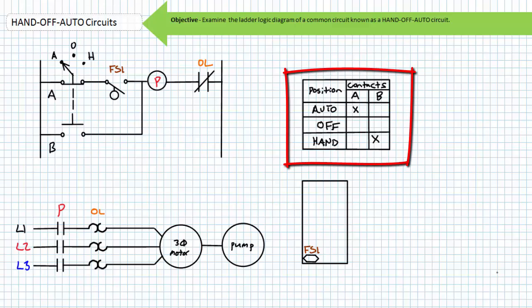The target table, sometimes called the contact chart for the selector switch, indicates A is closed in the auto position, neither contact is closed in the off position, and contact B is closed in the hand position.